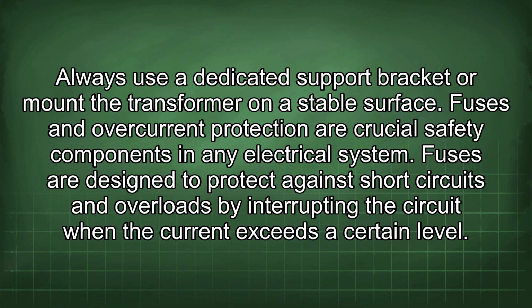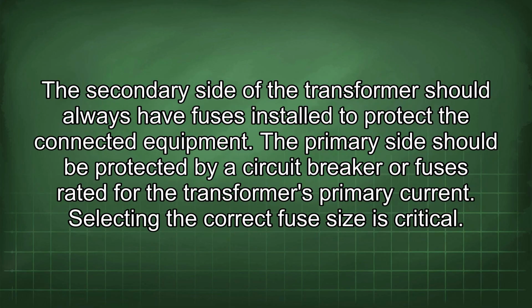Fuses and overcurrent protection are crucial safety components in any electrical system. Fuses are designed to protect against short circuits and overloads by interrupting the circuit when the current exceeds a certain level. The secondary side of the transformer should always have fuses installed to protect the connected equipment. The primary side should be protected by a circuit breaker or fuses rated for the transformer's primary current.